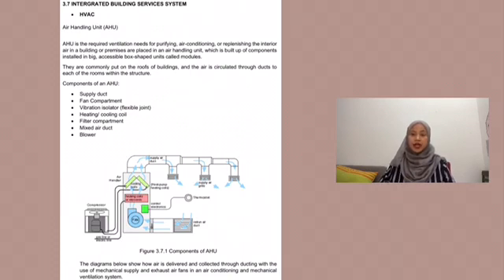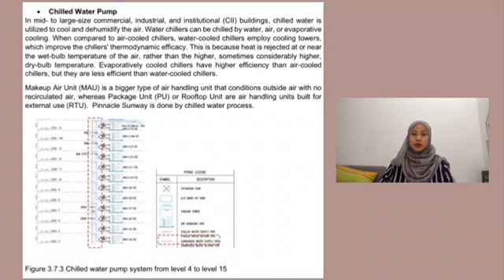HVAC component of an AHU is supply duct, fan compartment, vibration isolator, heating, filter compartment, mixed air duct and blower, chill water pump. In mid to large size commercial, industrial and institutional buildings, chill water is utilized to cool and dehumidify the air. Water chillers can be chilled by water, air or evaporative cooling. Evaporatively cooled chillers have higher efficiency than air-cooled chillers, but they are less efficient than water-cooled chillers. Make-up air unit is a bigger type of air handling unit that conditions outside air with no recirculated air, whereas package unit or rooftop unit are air handling units built for external use.